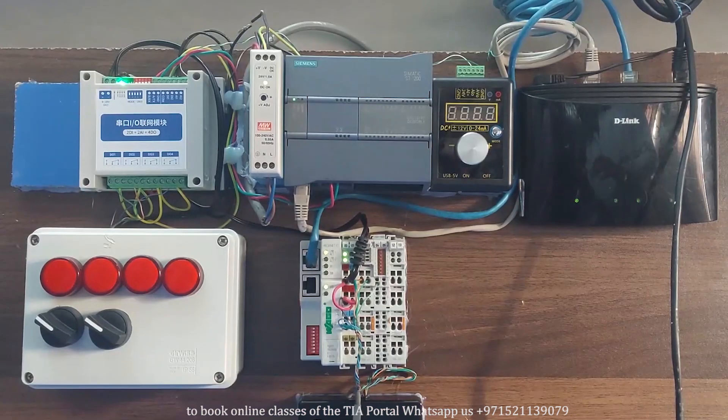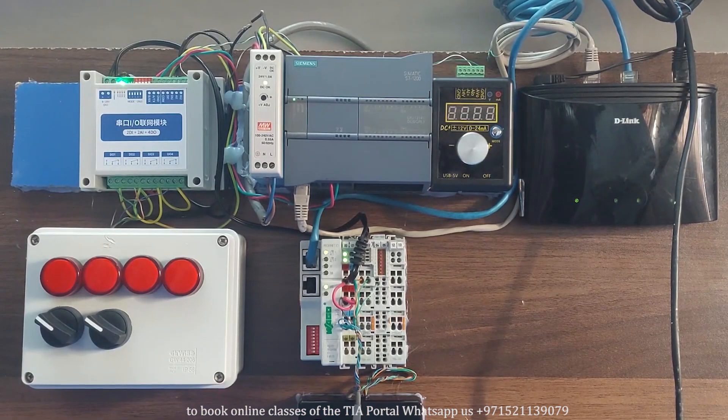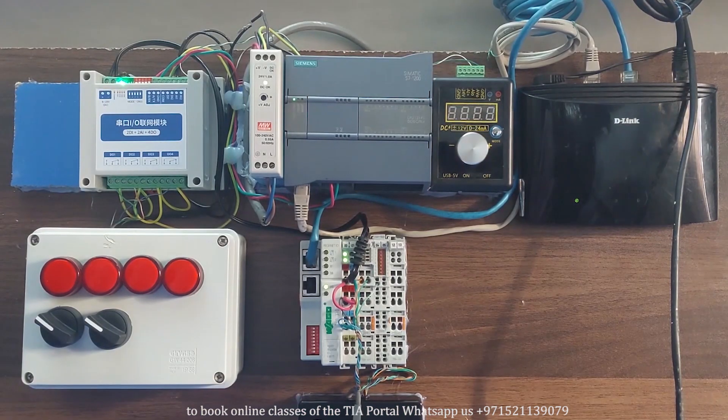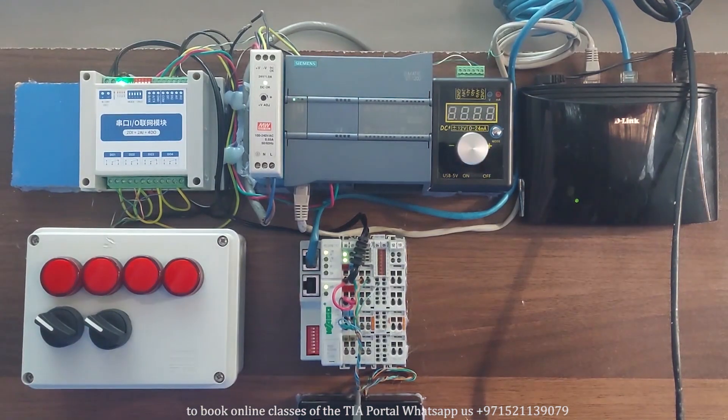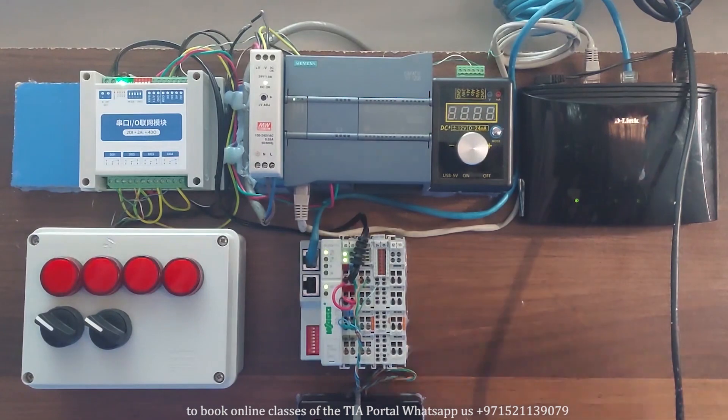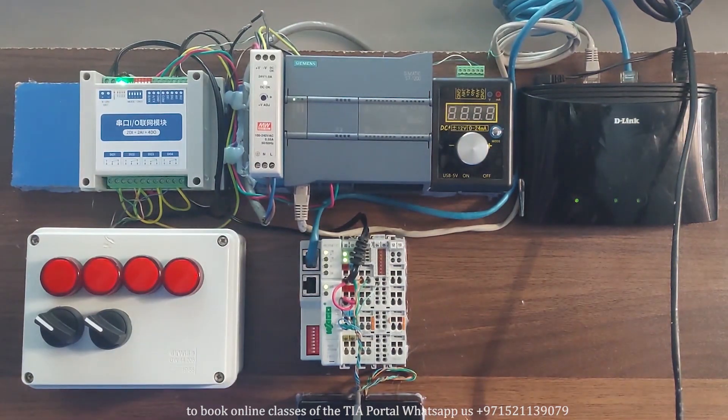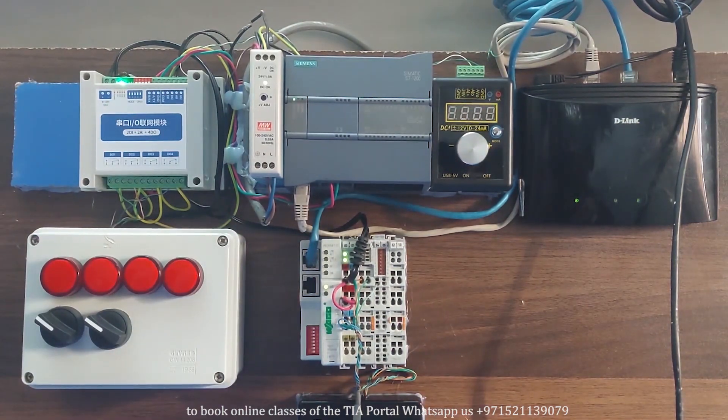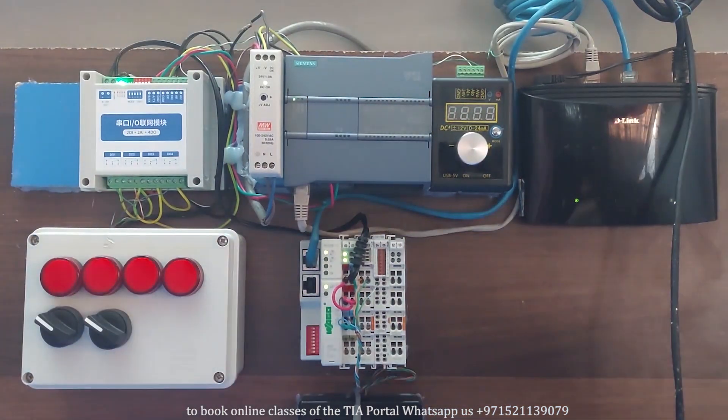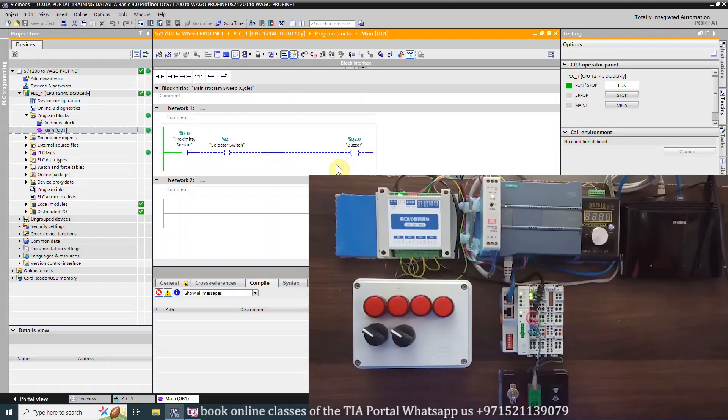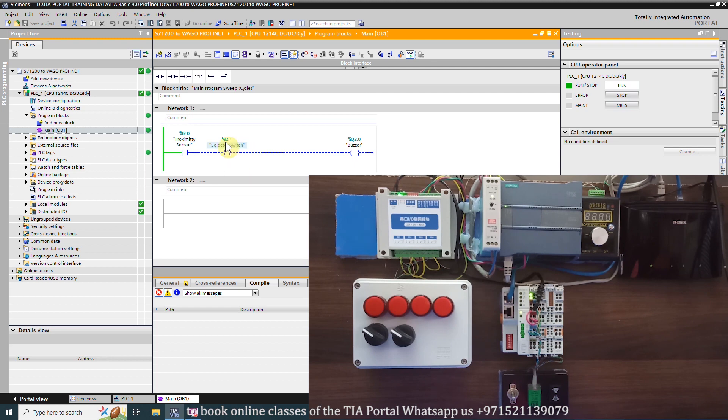As you can see that the communication between S7-1200 PLC and the WAGO fieldbus coupler is established over PROFINET. If we turn on the switch, its contact closes in the ladder program.